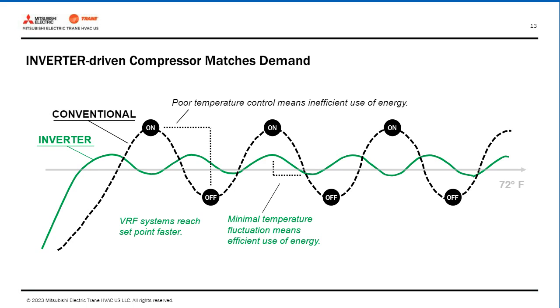while also maintaining the energy-efficient use of the compressors and also maintaining just a more constant space temperature rather than kind of creeping up. It feels like it's a little warmer, and then it turns on, and then it gets kind of cool. Rather than the constant cycling, having the compressors be active all the time helps minimize the deviance from the space set point. And the system uses the precise amount of energy required to meet each zone set point. So this translates to efficiency and operational cost savings, as well as less temperature swings with increased level of comfort for the individuals in the space.